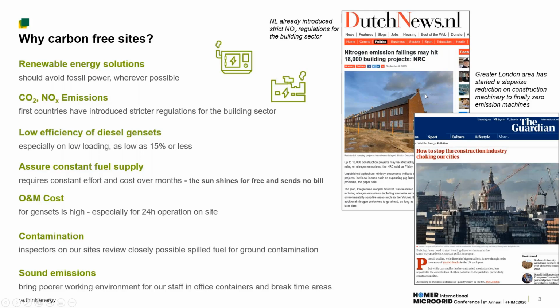Besides these external factors, looking at the genset itself, we see quite low fuel efficiency, especially for low loading, which we often see on construction sites. Here we are at maybe 15% or sometimes even less fuel efficiency, which is not very motivating to use it.